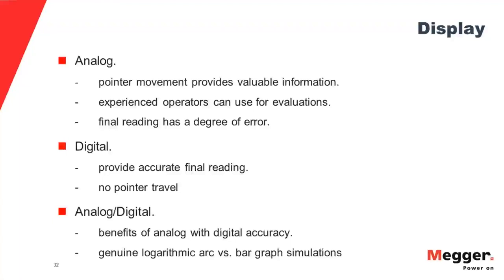So that was the value of pointer travel, and your experienced operators loved to see that. In a lot of cases, that's all they looked at. Digital, on the other hand, when the pointer stops, then you have to figure out what that is actually telling you, because it may stop between lines on the arc. And so it's between the 5 megohm line and the 10 megohm line. So is it 7 megohms? Is it 8 megohms? Whatever. So there was a certain amount of guesswork in that. Now the digitals eliminate all of that. They give you the number dead on, but you don't see pointer travel.